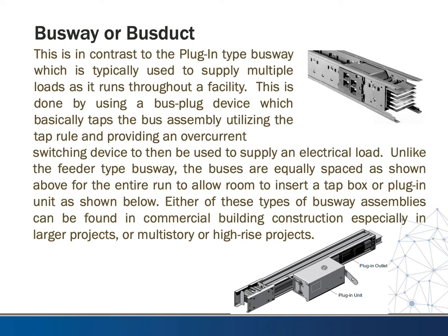So this is in contrast to plug-in type busway, which is typically used to supply multiple loads as it runs throughout a facility. This is done by using a bus plug device, which basically taps the bus assembly utilizing the tap rule and providing an overcurrent switching device to then be used to supply an electrical load. Unlike the feeder type busway, the buses are equally spaced as shown above for the entire run to allow room to insert a tap box or plug-in unit as shown below.